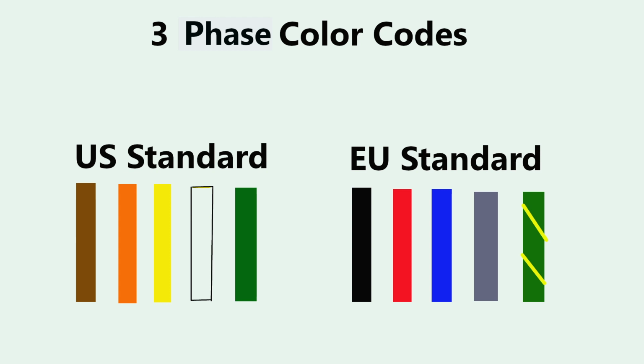Let's talk about color codes for three-phase power. Three-phase power in the United States is normally brown, orange, and yellow. It's easy to remember because it's BOY, boy. If there is a neutral, it will be white, and green will be ground. The European color code is black, red, and blue. Black would be phase 1, red would be phase 2, blue would be phase 3. And gray would be the neutral, and green with a yellow stripe would be the ground. What we normally do in the US is usually run black wire most of the time, and we put colored tape around the wire near where it's connected, brown, orange, and yellow, and that's typically how we identify the three-phase power.